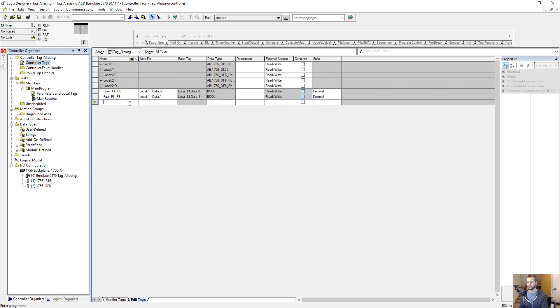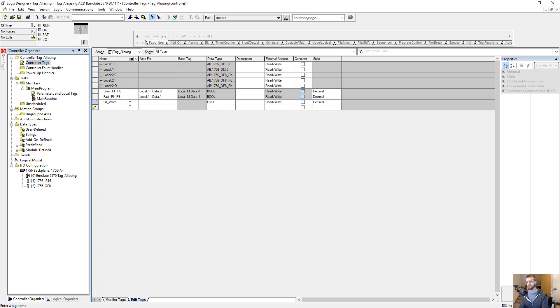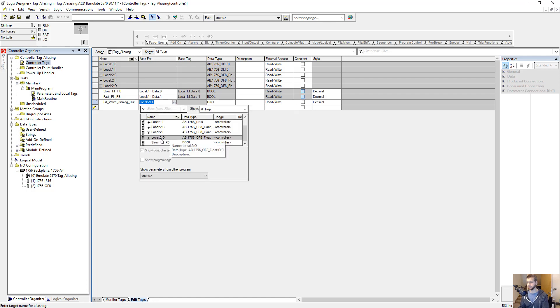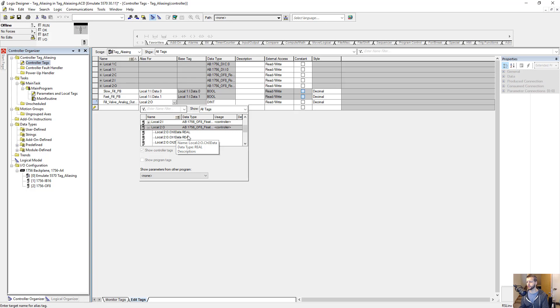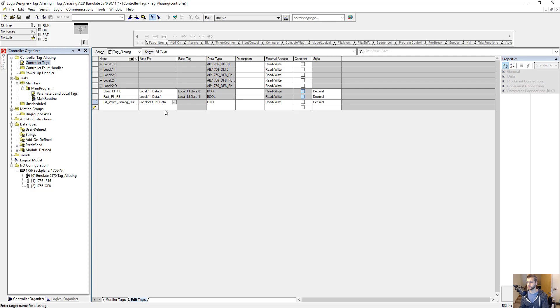Our final tag will be the fill valve that we're opening and closing to fill the tank. We'll call this fill valve analog output, and it's in slot 2. So we use local colon 2 colon O. This syntax is slightly different — if we expand local colon 2 colon O, we have CH0 data, CH1 data, and so on. We want CH0 data. Again, this will fill in whatever the data type is of this alias tag. I hit enter and it makes it a real.